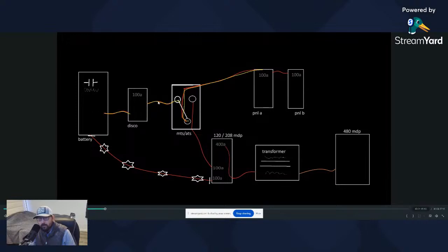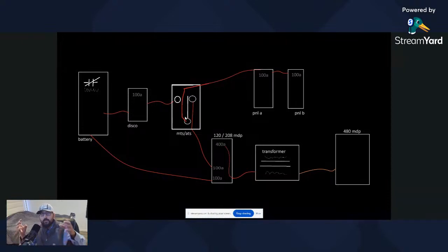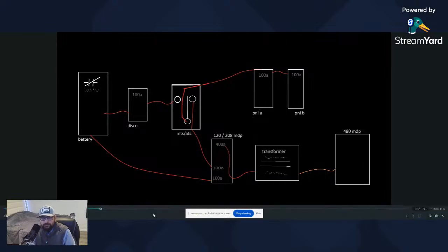You can see where we're now on this left side, we're going back to the common and then feeding these panels. And now we're pretty much on emergency power right now. So that's kind of how that works. So right now we have regular power, everything's cool. Battery is not hooked up. You can see where it's maintaining charge because we want to maintain voltage to this cabinet. The power is still flowing here, power is still flowing here, but the switch is not activated. So that's how we're not creating a phase to phase explosion pretty much, is that this still has power. So once we lose power, this switch is here, the battery supplies these loads.